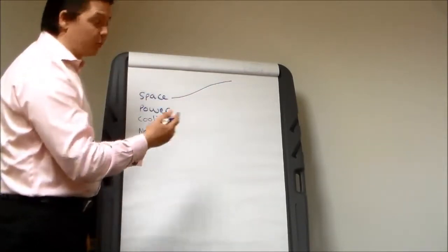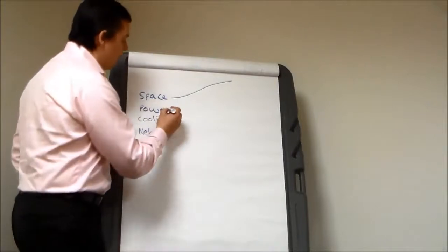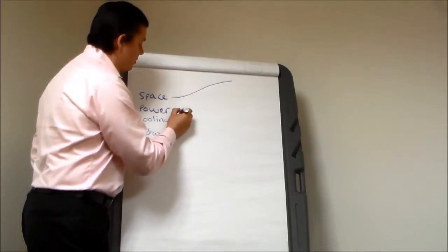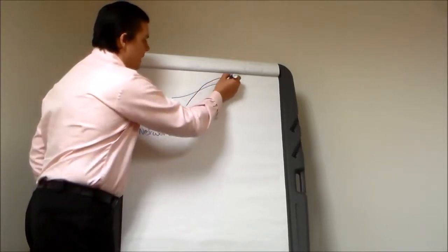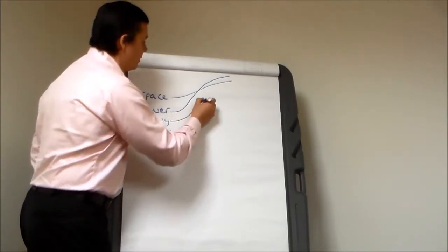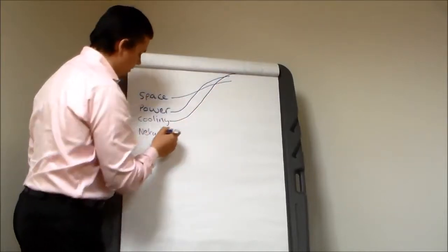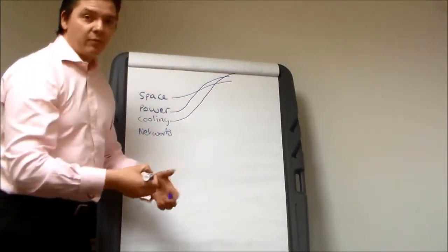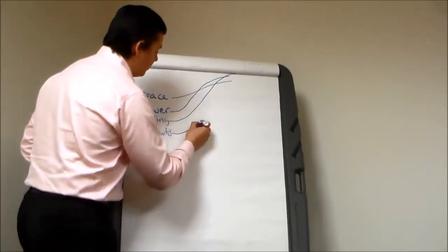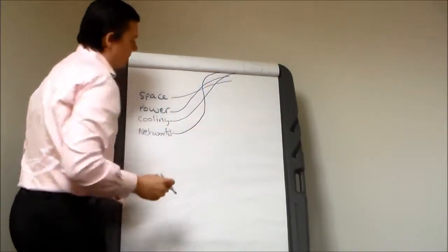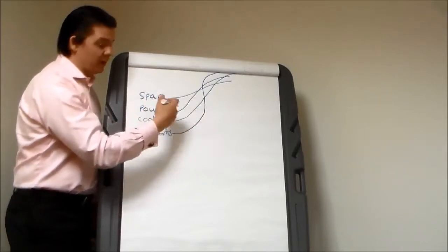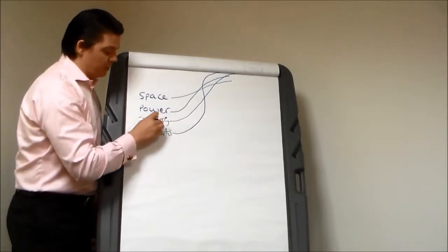Space generally can be going up, could be going down if they're doing virtualization. Power will definitely be going up whether they're doing virtualization or consolidation, because they'll be using more kit. Cooling, when power goes up, generally follows it on the same line. Networks, when I add more servers, or even virtual servers, I'm going to end up using more networks. So these things all move up. Servers potentially move down on the physical side, but these will generally go up.